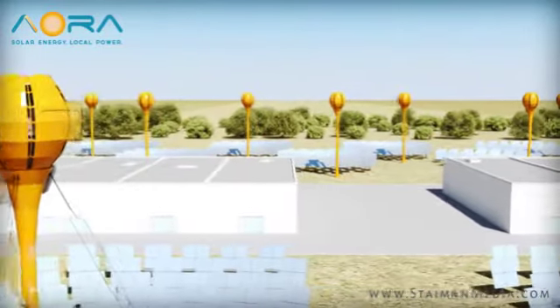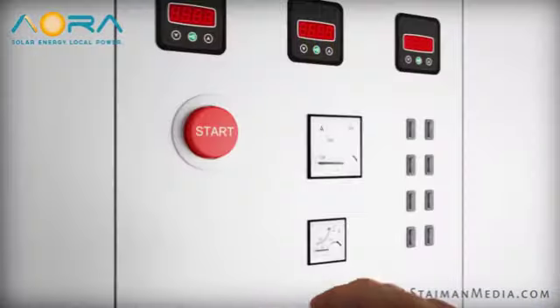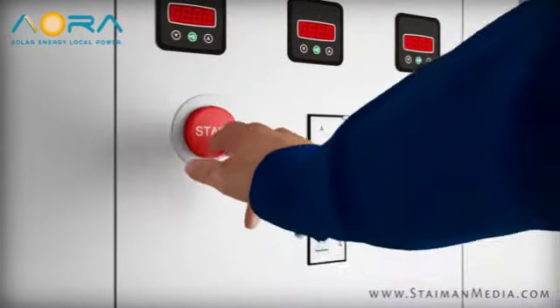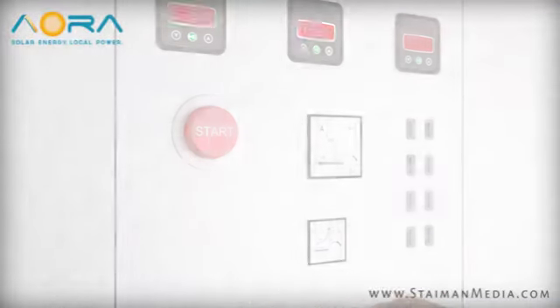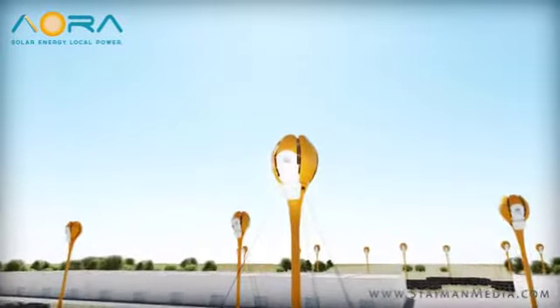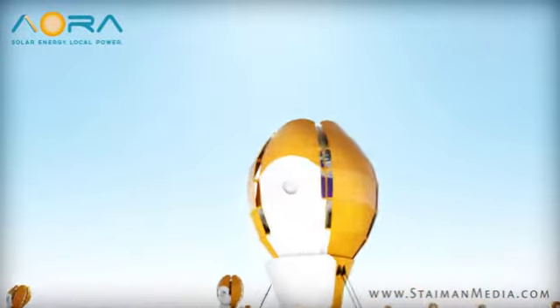The sun's clean, limitless power reflects off of Tulip's perfectly positioned array of heliostats. The system is powered on via the AORA control room, either in person or remotely. The tower's lens receives the rays reflected off the 50 mirrors. Inside the unit, the intense 1,000 degrees Celsius temperature is used to superheat already pressurized air running through the turbine tower.